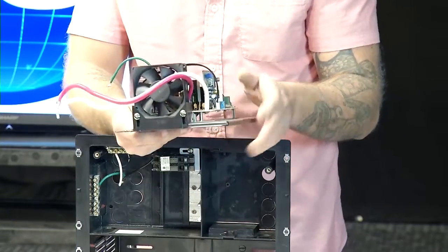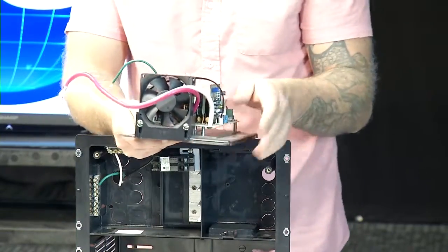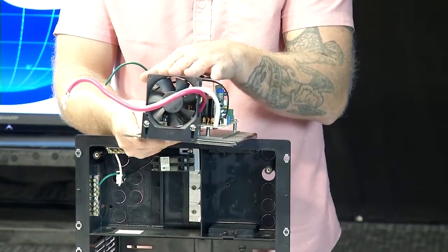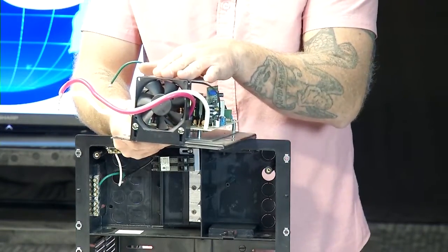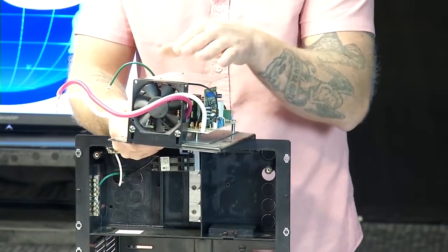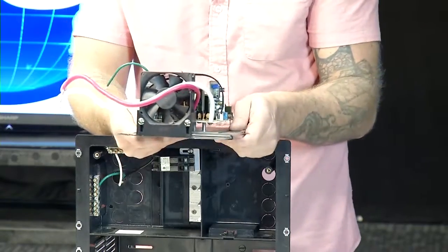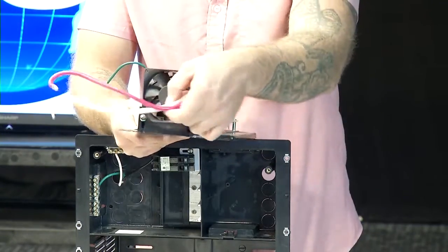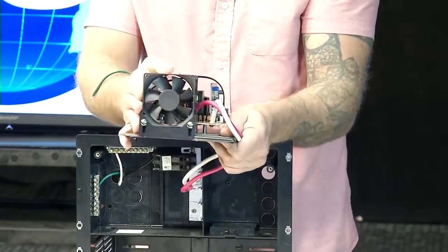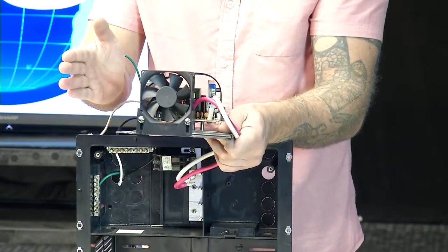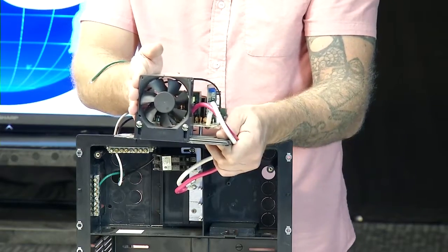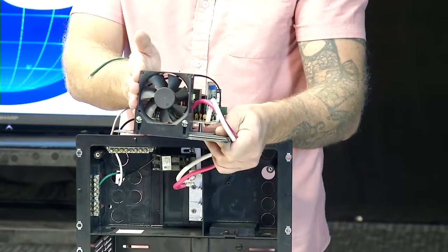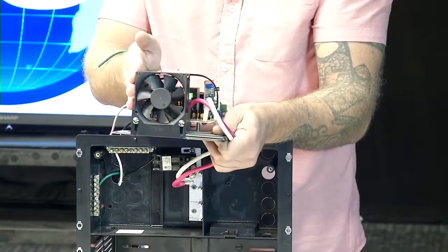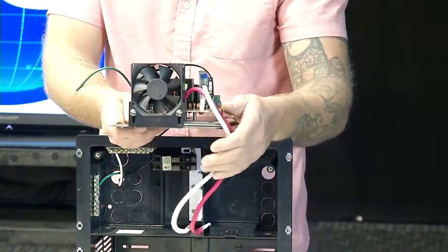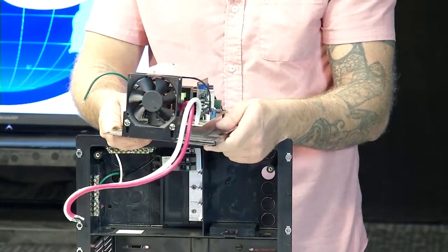One difference between our product and some of the other products out there is our fan is not temperature based. Our fans are load based, meaning the load from your 12-volt lights, water pump, furnace, or any 12-volt loads. After a certain load, this fan will start running. It's not going to start running just because it's hot. So if your fan's running, that means either your battery's charging or you have some lights on.